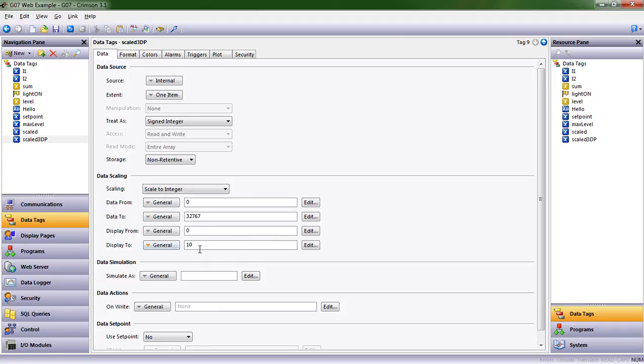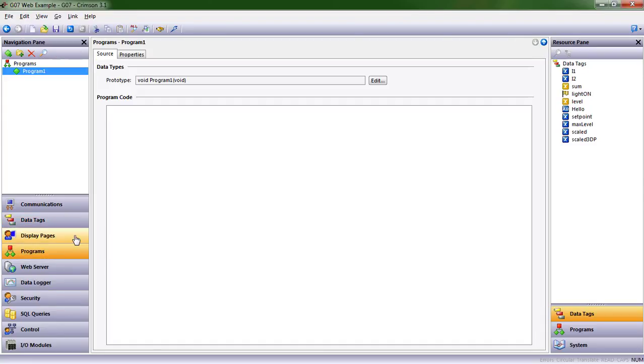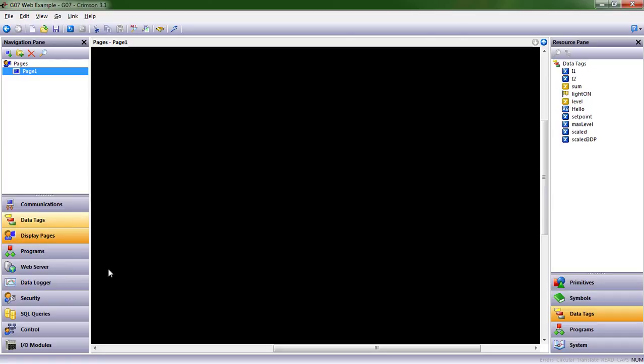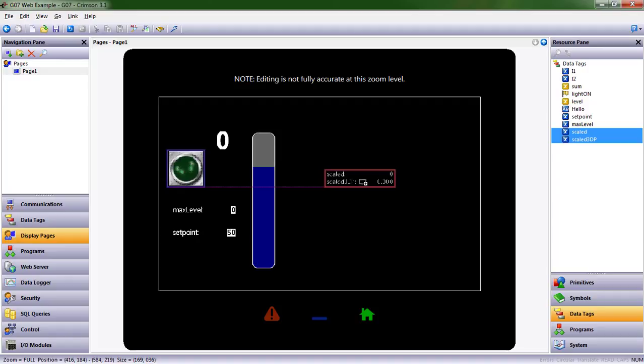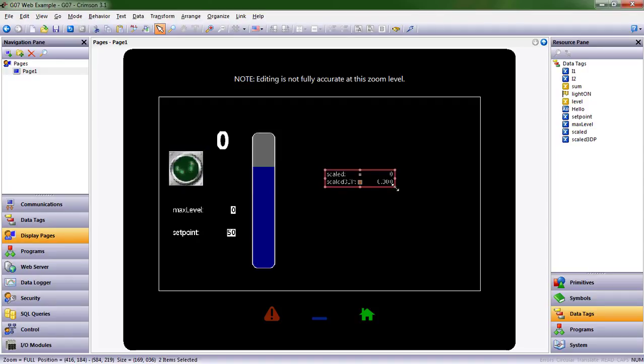We have to do one more thing. Right now, this 10, because I added those three decimal points, is actually 0.010. I need to give it those three extra spaces. So now, the data coming in, 0 to 32,767, is going to be scaled to 10.000. Let's see what that looks like on the screen. I'm going to put my scaled and scaled 3DP out here, make them bigger, and change the font size.